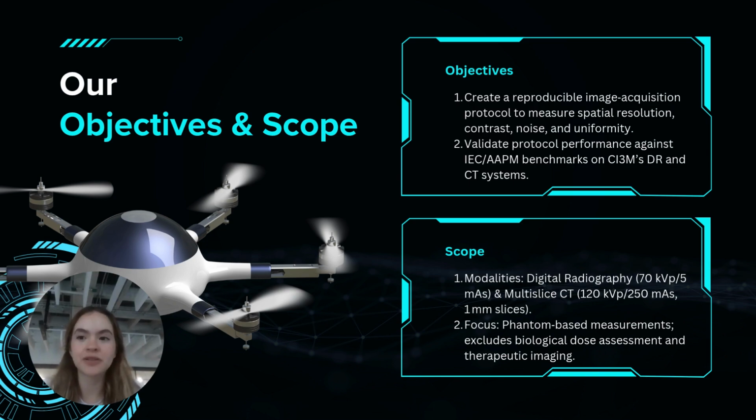Our objectives are twofold. First, to develop a reproducible protocol that measures spatial resolution, contrast, noise, and uniformity. Second, to validate our results against international IEC and AAPM benchmarks on our learning partner's digital radiography and multi-slice CT units.